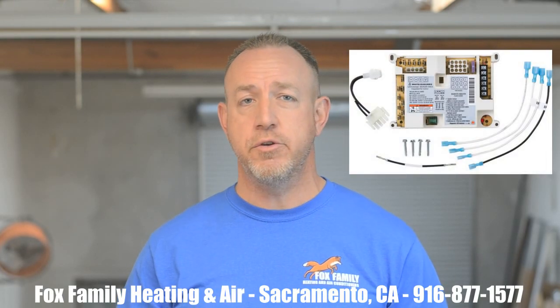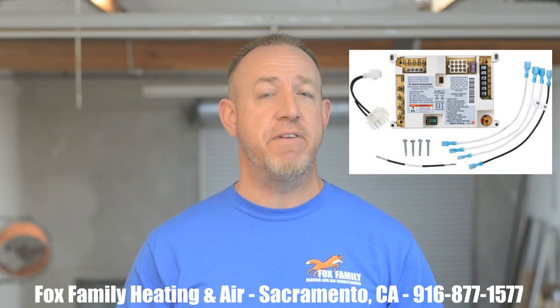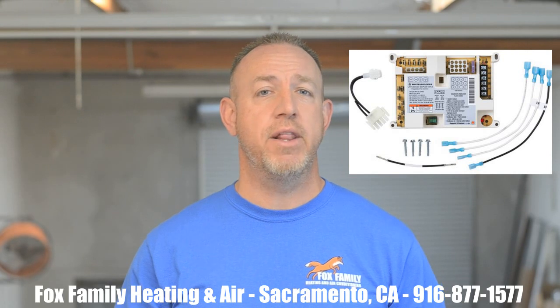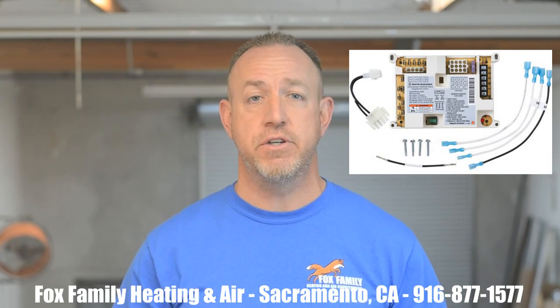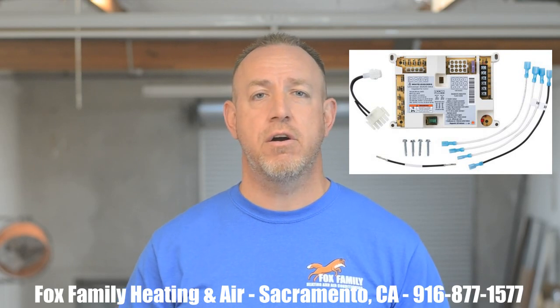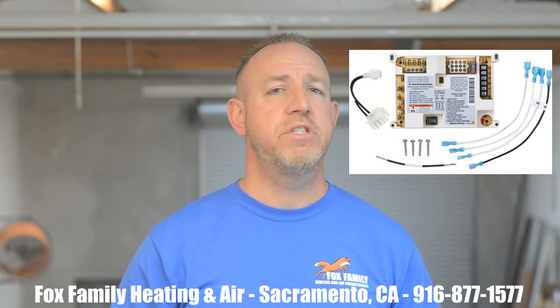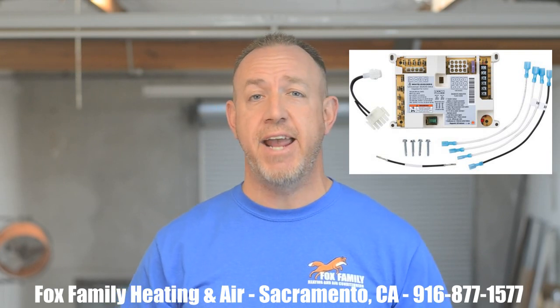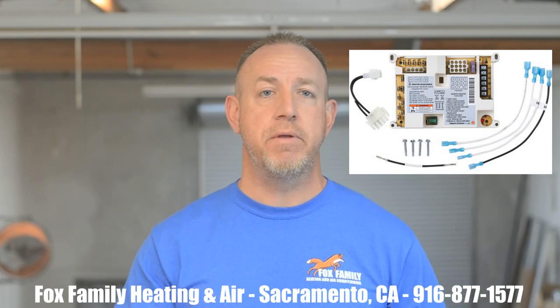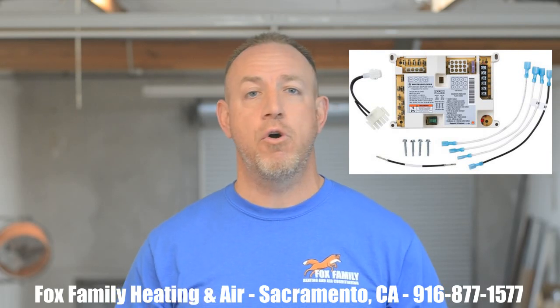A prime example of this is one of the control boards we use, the White Rodgers 50A55-843 control board. It's a universal replacement that we like to use for most single stage gas furnaces in the residential field. Most of the time, control board changes are like-for-like changeouts, plug and play. Well, when you use this board to replace the Trane XB80 gas furnace control board, there's an adapter you have to use from the box to include a couple of rollout switches into the Molex connector that plugs into the board.